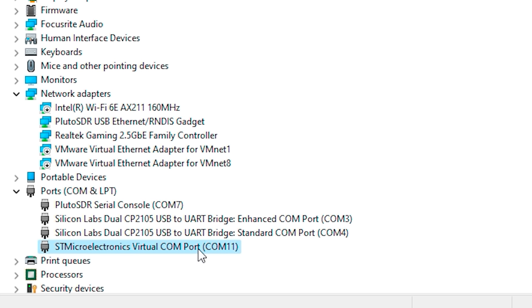Once the driver is installed and the RF power meter is plugged in you should see the device listed in your device manager with a description of an STMicroelectronics Virtual COM Port. Just make a note of the COM port number.